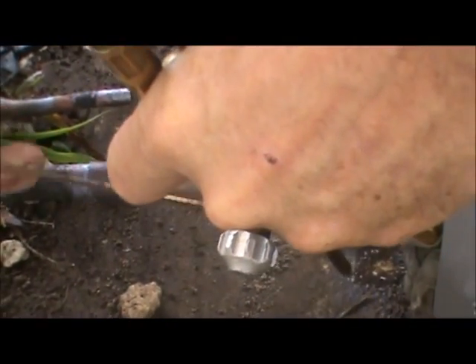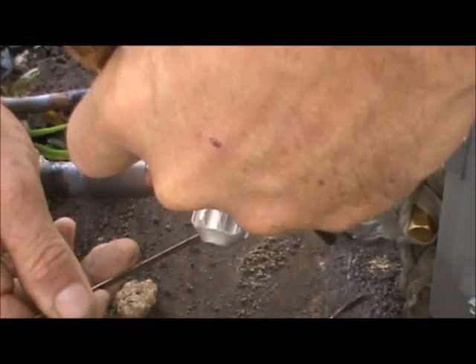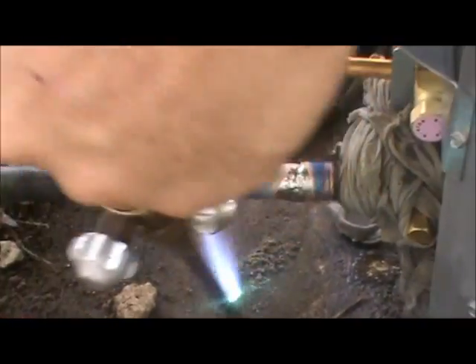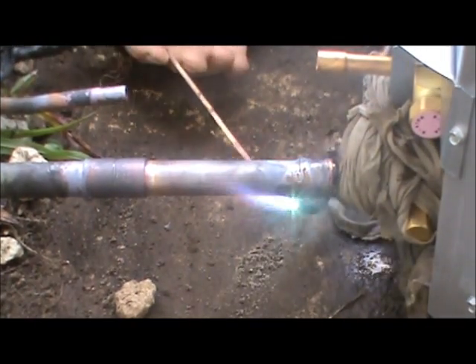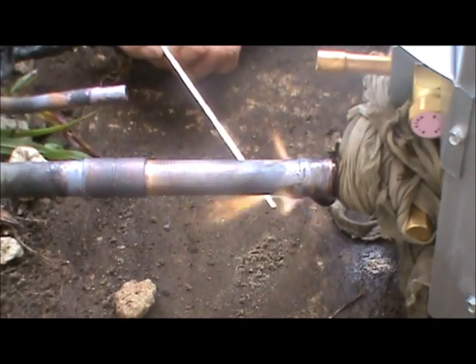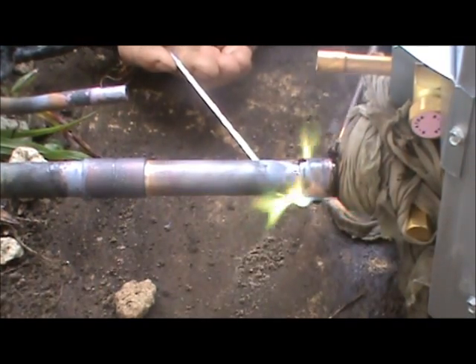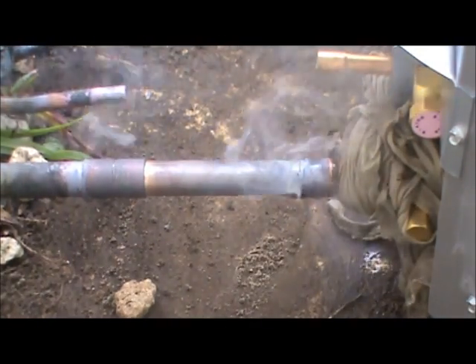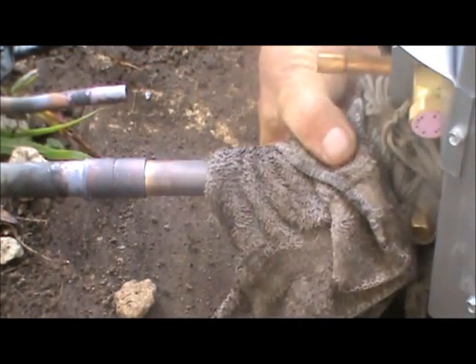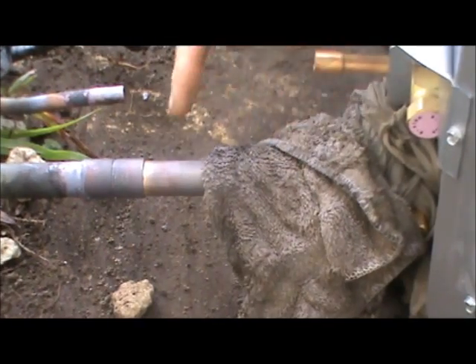This is where it gets a little difficult when you have different angles and you can't see exactly what you're doing. You just want to push the brazing rod into the joint, and that brazing rod and the Sil-Fos will follow the heat. This is hot, so we'll get this cooled down as quickly as possible. We have one more joint to do right here.